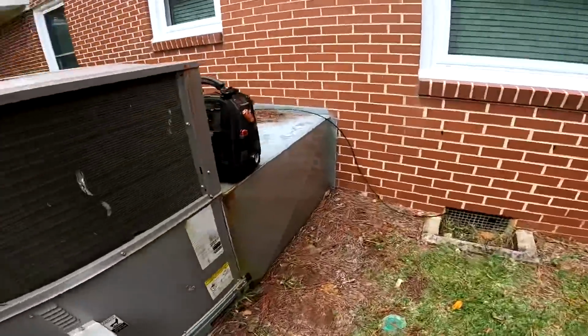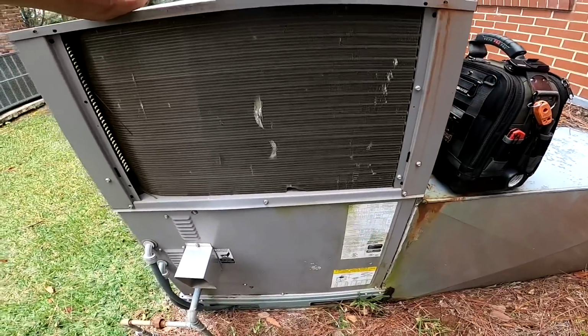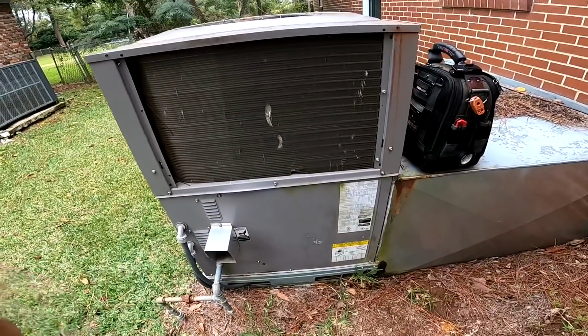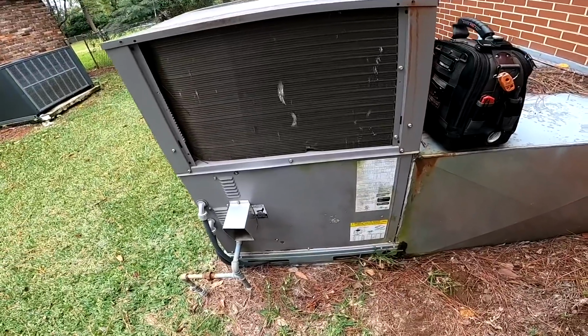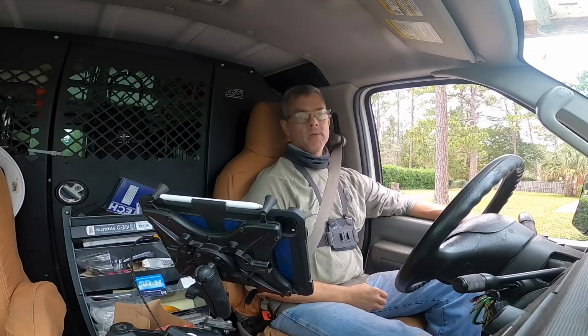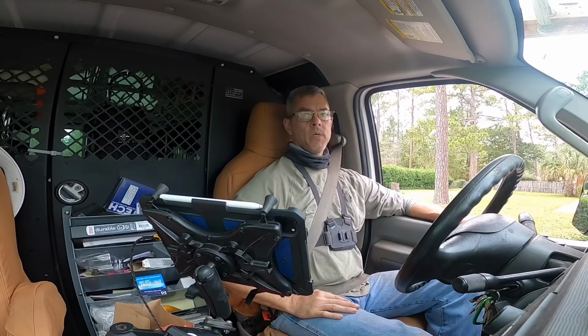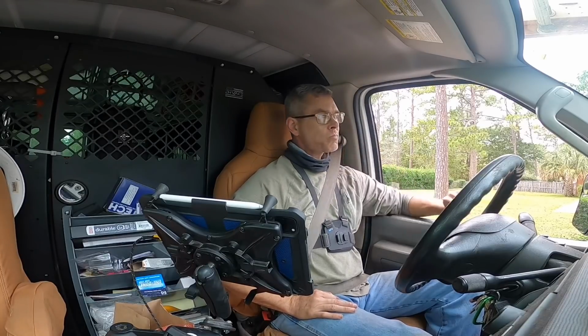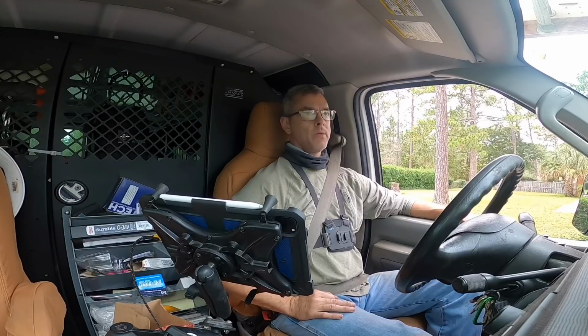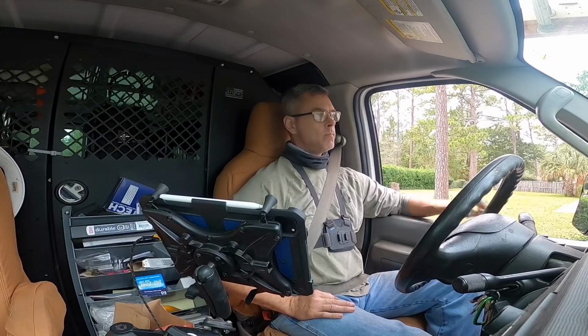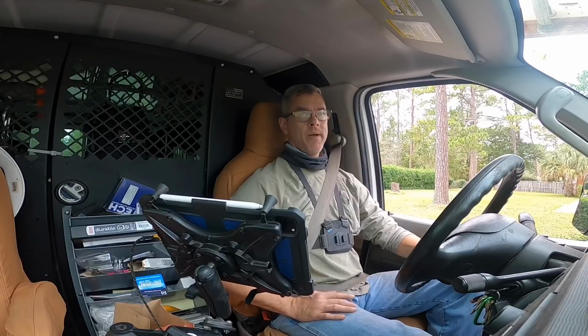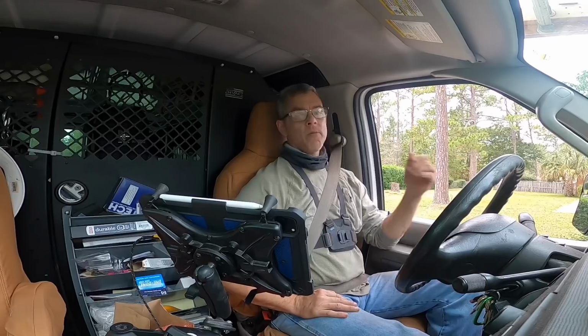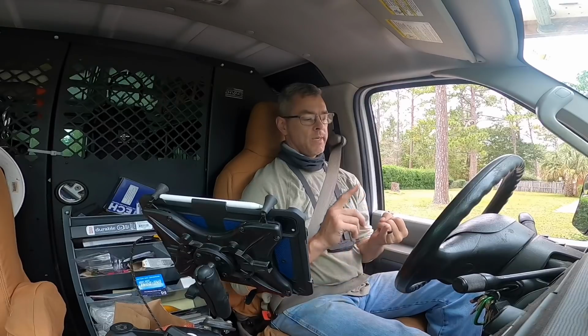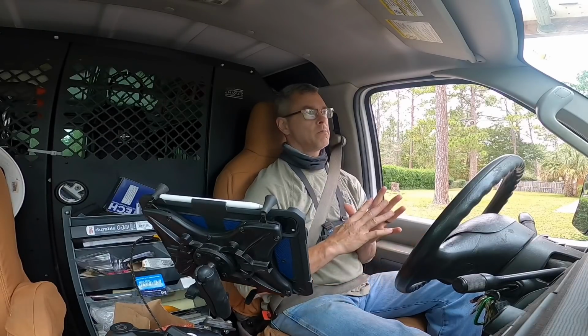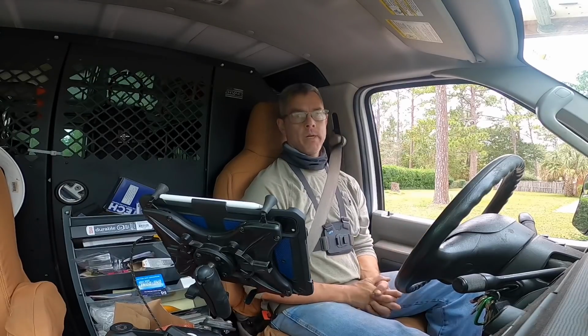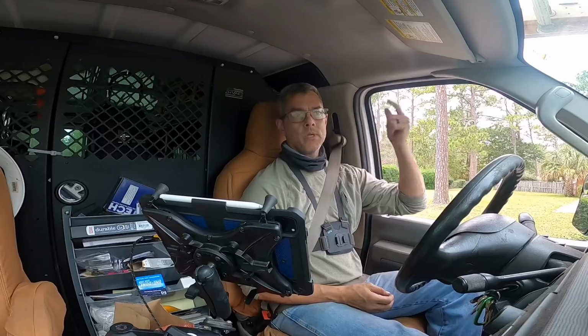The rust spots I saw on parts of that heat exchanger were just too bad for me to say, well, it ought to be good for another year. I'm just not comfortable doing that. All right, on that one, I just did not feel comfortable letting him go through another heating season with that heat exchanger. I saw too many spots on it that looked like they could rust through at any time. So that was just a judgment call on my behalf. I felt like I would feel more comfortable if my customer had a new heat exchanger, new draft motor, and everything was fixed right.